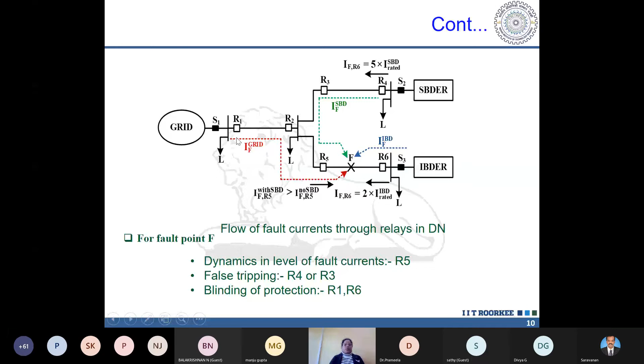And blinding protection is the last concept, as I said, R1 and R6 will see this. Why? Because for this fault point, the grid will contribute some current, and the SBDER also contributes current, IBDER also tries to contribute some current. As a result, the fault contribution from the grid side diminishes, the fault current magnitude from the grid reduces. So the relay R1 will see a very small amount of current, and it will not trip, that kind of situation arises.